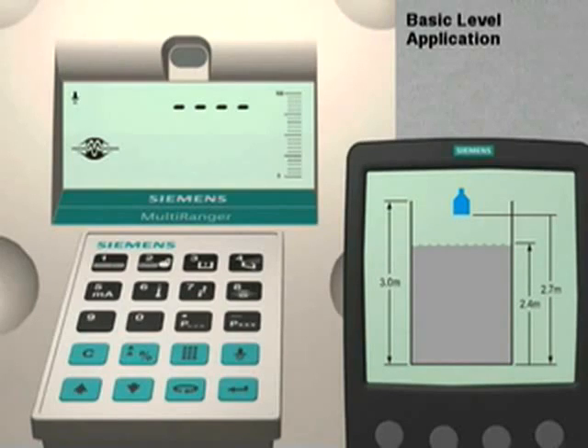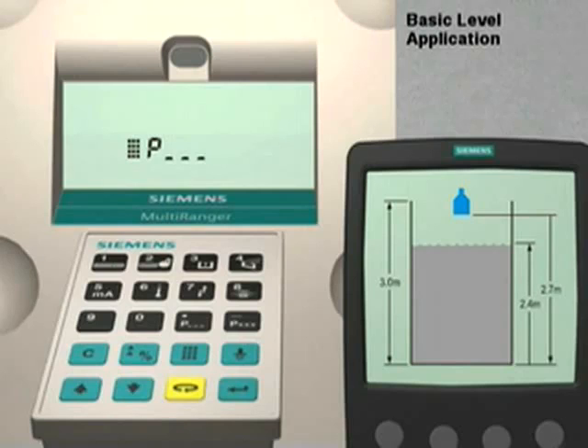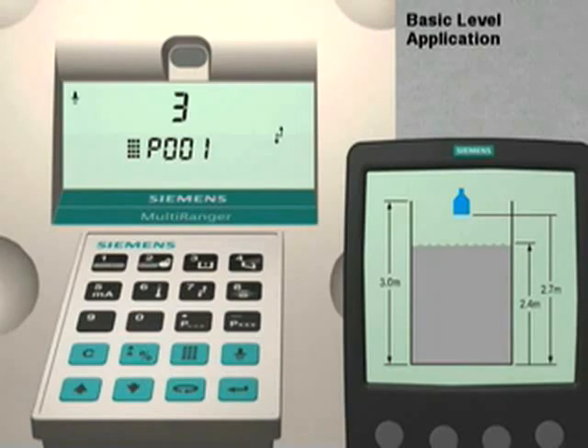The first step is to put the multi-ranger into program mode. Push the mode key, then the next display key twice until the multi-ranger displays P dash dash dash. We then enter 001 for parameter number 1.